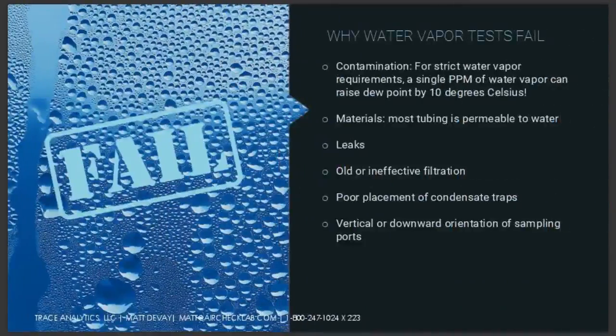All right, so why do these fail? Contamination is probably the number one reason why a water vapor test will fail. A very small amount of water will make a very big change in your dew point, particularly at stricter classes. So if you're trying to get a class 1 or a class 2, for instance, 1 ppm at class 2 will raise your dew point by 10 degrees. It's a very tiny amount of water that has a very big effect on your reading. A fingerprint on your equipment can retain enough water to make the difference between passing and failing.